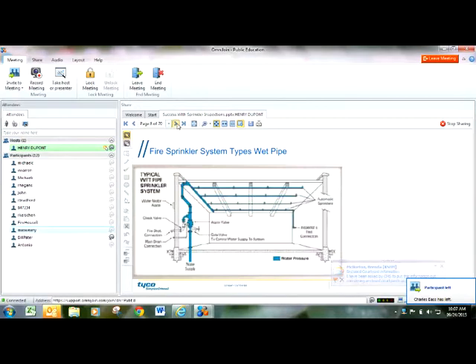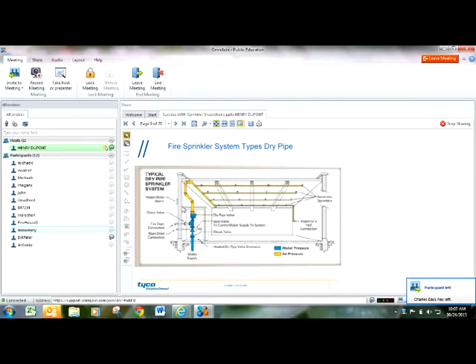The other most common sprinkler system is a dry pipe sprinkler system. The components of a dry pipe sprinkler system are almost exactly the same as a wet pipe sprinkler system. However, you have a dry pipe sprinkler valve, and my arrow is pointing to it right there. How a dry pipe sprinkler system works is you have an air compressor.